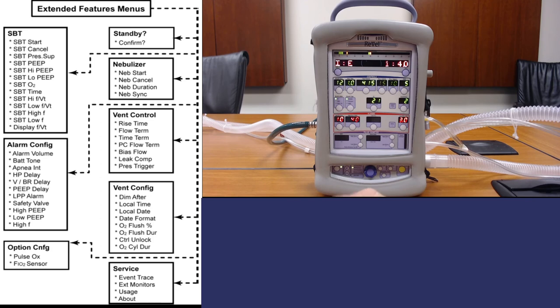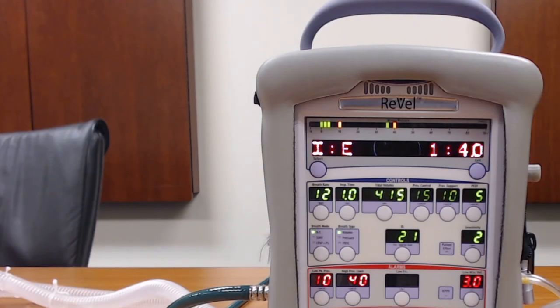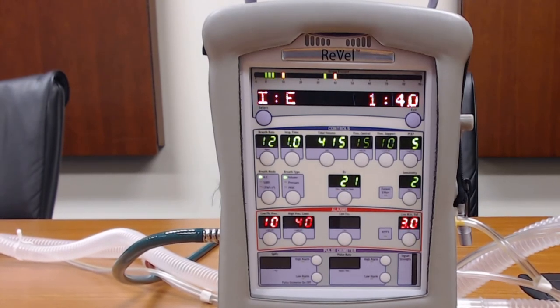The bias flow is something you'll typically need to adjust if you're trying to utilize the nebulizer function — it may give you an error message saying the bias flow is under 10. You would need to go into this menu and change the flow; typically it'll be set to 5. If you do a new patient, it defaults back to 5, so you would have to change it to 10 using the selector knob and then hitting select. To exit the controls, just hit exit until you start seeing the parameters displayed on the display. That is how you access the extended menus on the CareFusion ReVel Ventilator. Thank you for watching and I'll see you in the next video.